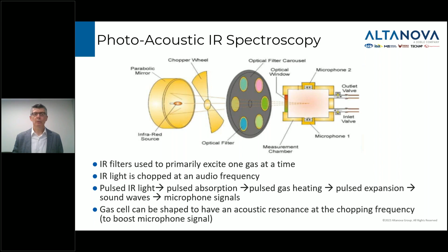Once again, there are some advantages and disadvantages of this approach. As in all the IR techniques, some models can be compromised in their accuracy if there are interfering gases present in the sample. Adding more IR filters is a way to get more spectral information and to combat that issue. Some models have been known to drift over time, and some need major service after 3 or 4 years of continuous operation.